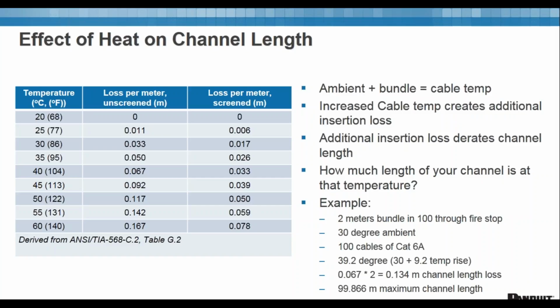This is taking it a little bit further, just effect of heat on channel length, and this is just looking at the loss per meter unscreened and the loss per meter screened at these different temperatures. So I already walked you guys through it. What you really see here is that, again, there's a very minimal impact on your overall channel length if these temperature rises are only seen in very small locations.